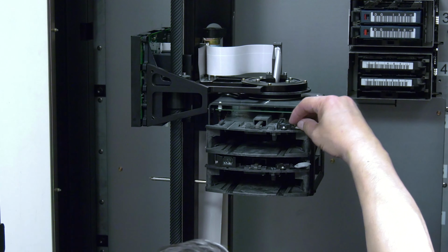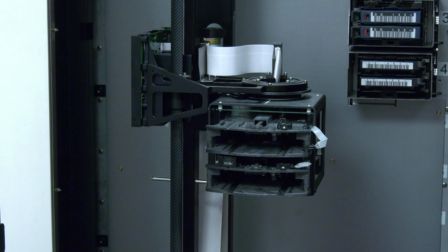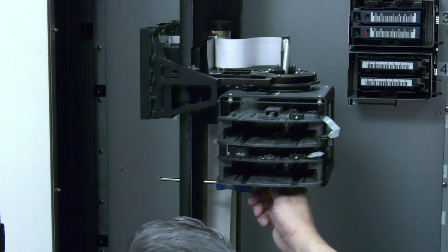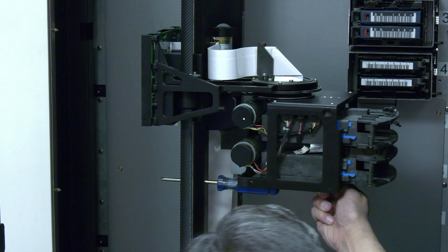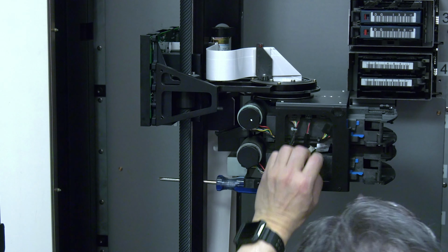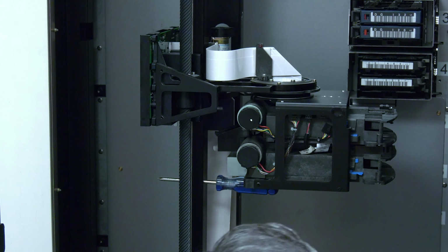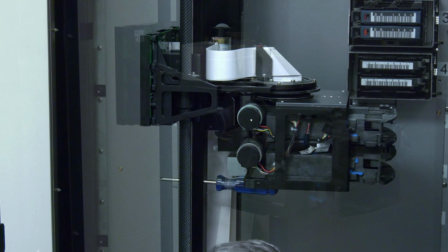To start, you will need to unhook the front sensor from the top gripper. Then, you will turn the entire gripper cage to the right and locate the motor plug for the top gripper and unplug that as well. Then, while still having the gripper cage turned to this side, locate the blue slide lock that secures the gripper into the gripper cage and slide it backwards until it clicks.